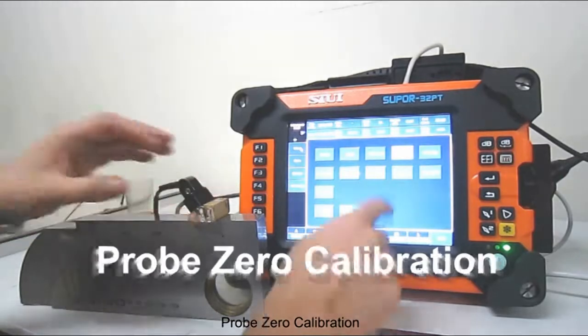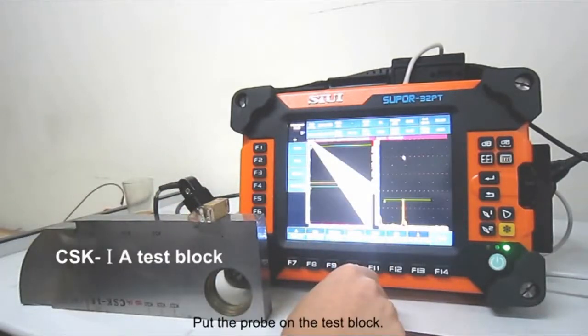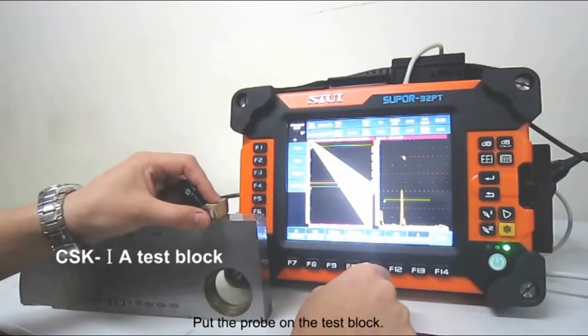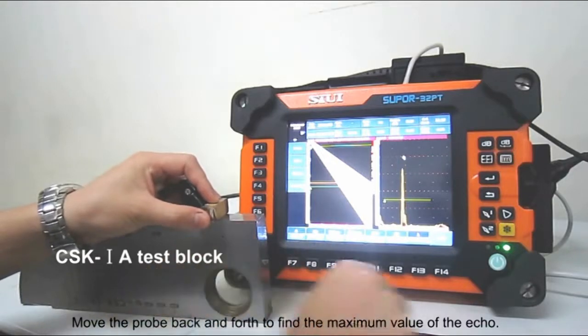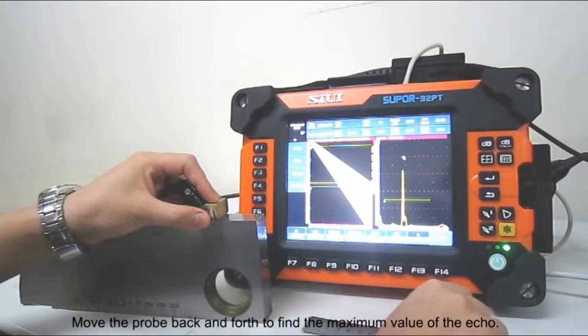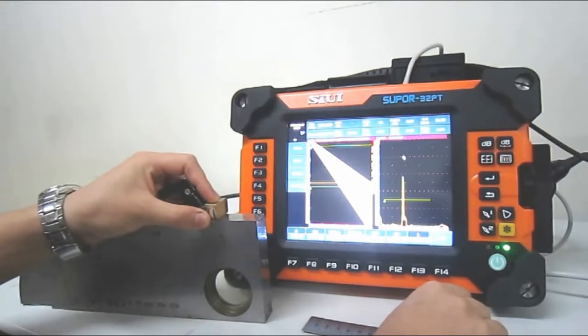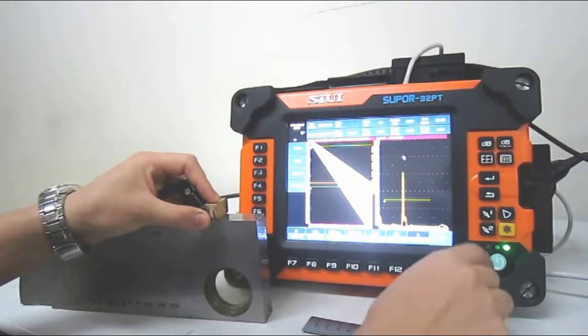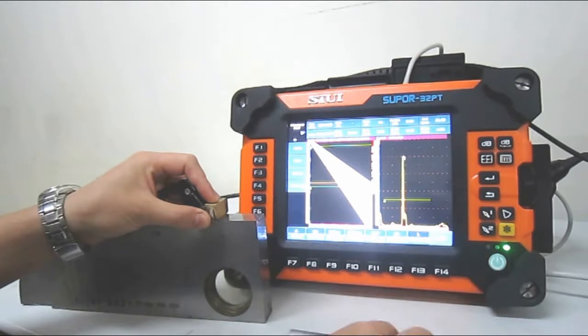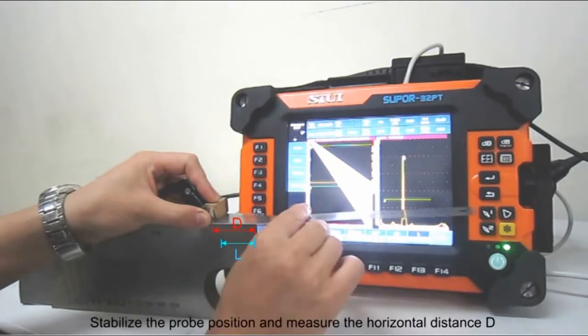Probe 0 calibration. Put the probe on the test block. Move the probe back and forth to find the maximum value of the echo.